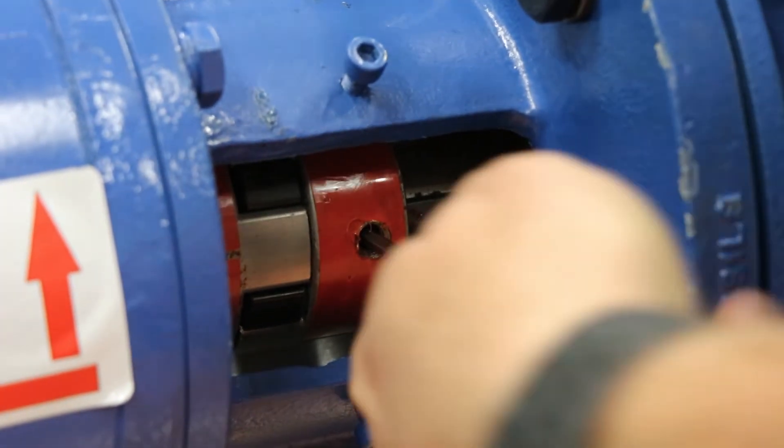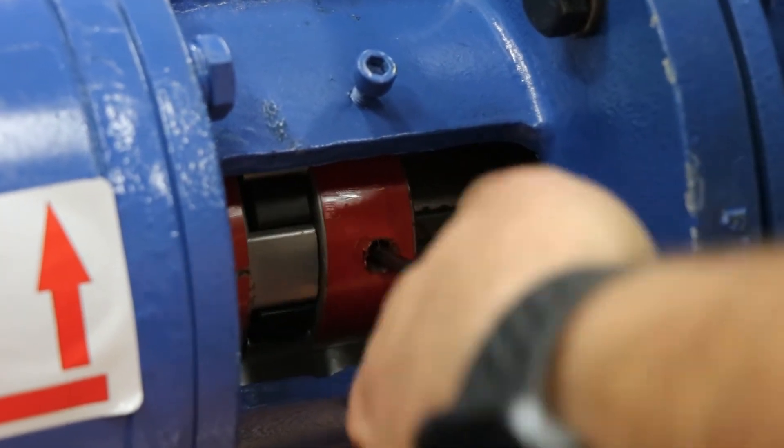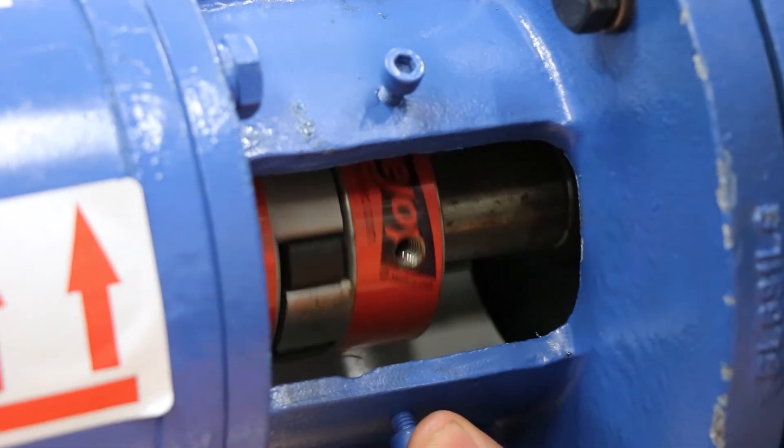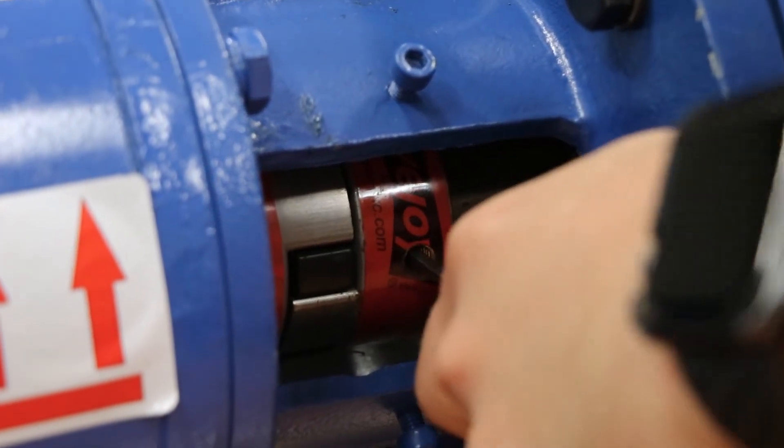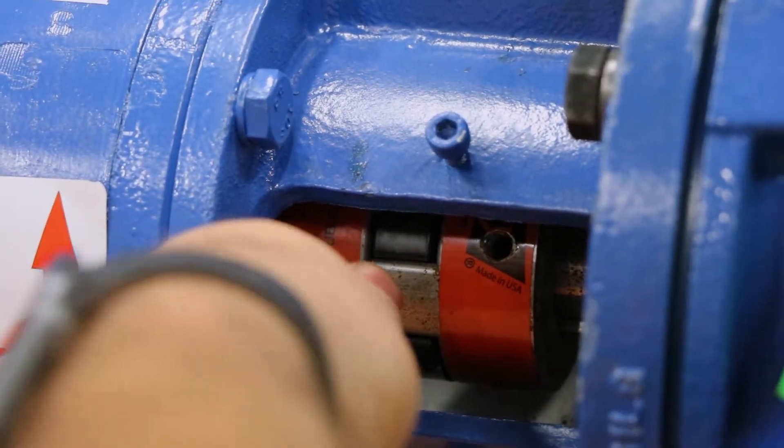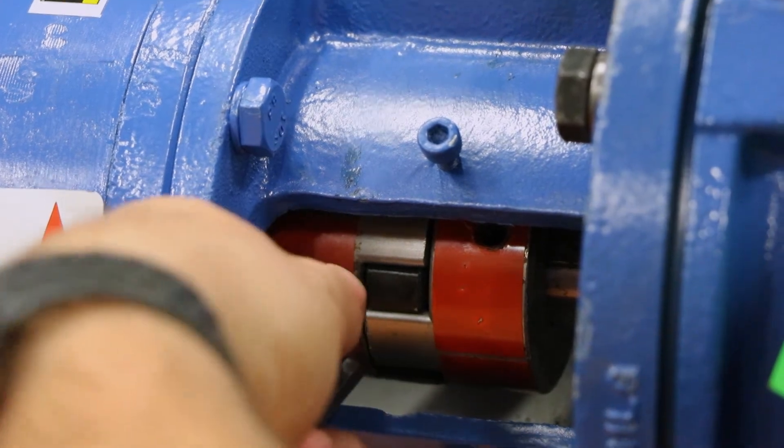There are two set screws on each half of the coupling. You want to go through and do the first one, then rotate the shaft 90 degrees to get to the second one. Tighten up both, get them nice and snug. Then you want to do the same thing to the reducer side as well. They also have two set screws both at 90 degrees apart. Go through, tighten up both set screws, and you're good to go.